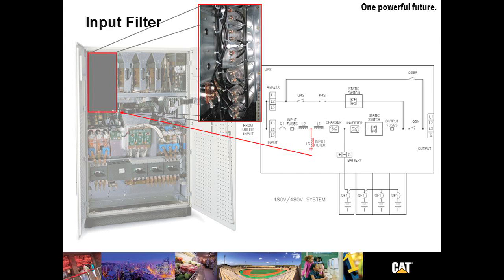This is a low capacitive input filter which protects against leading power factor. At 225 kVA, the THDI levels are reduced to less than 8%.